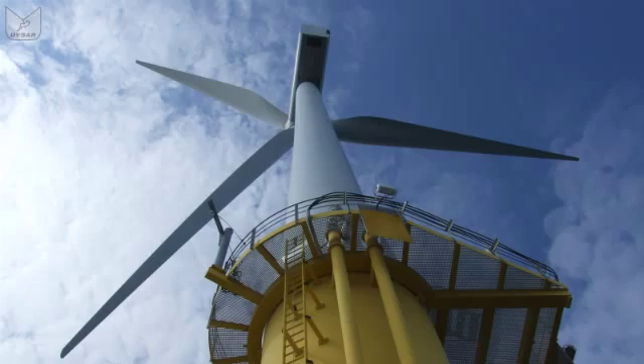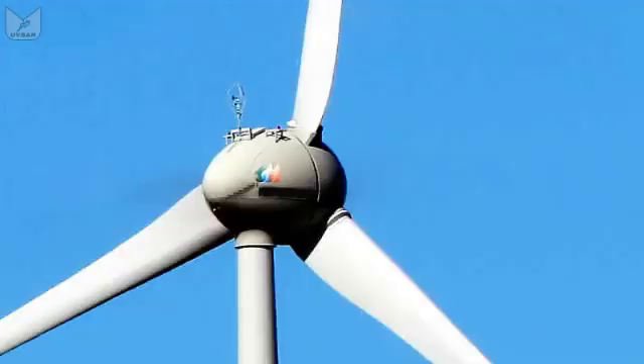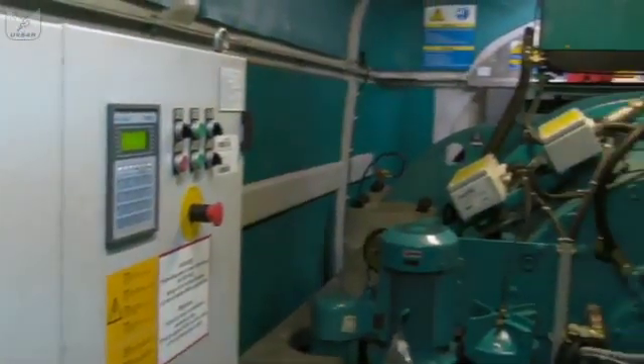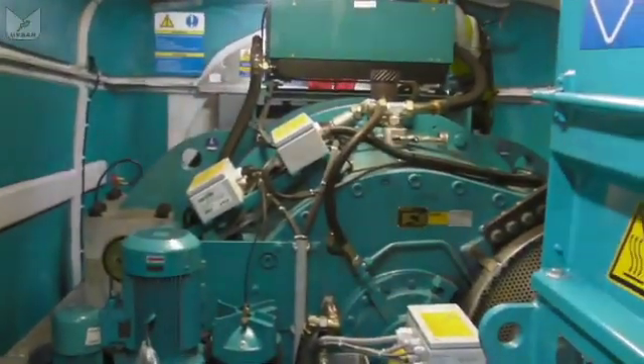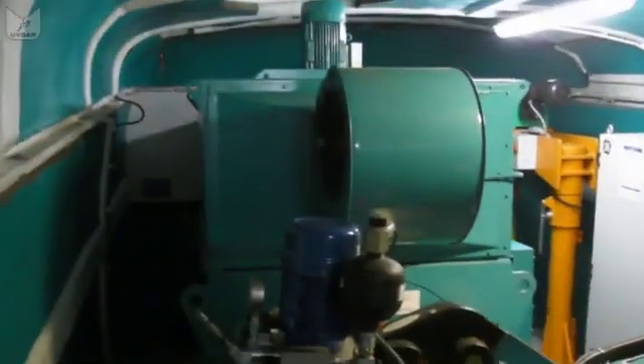The layout of a multi-megawatt nacelle is, again, more variable than for a smaller version. We always have to have a generator, but we may not have to have a transformer. In a few cases, such as the famous Enercon egg-shaped nacelle, we don't even need a gearbox. They're direct drive. We just have a shaft linking to a motor, and then lots of extremely complicated electronics to condition that power for connection to the grid. But in most cases, we need the same as we needed in the small turbine. Gearbox, generator, possibly a transformer, all in a fiberglass box.